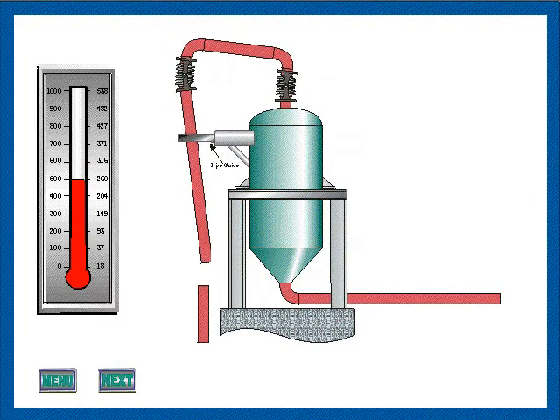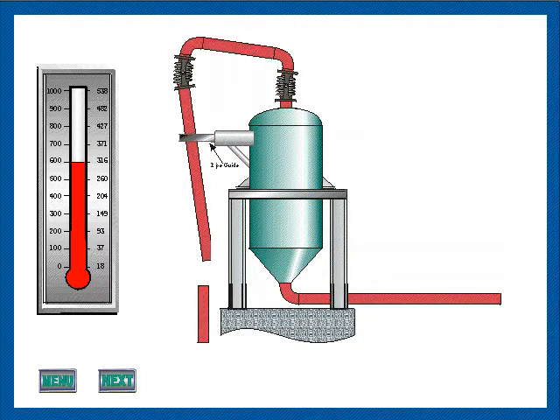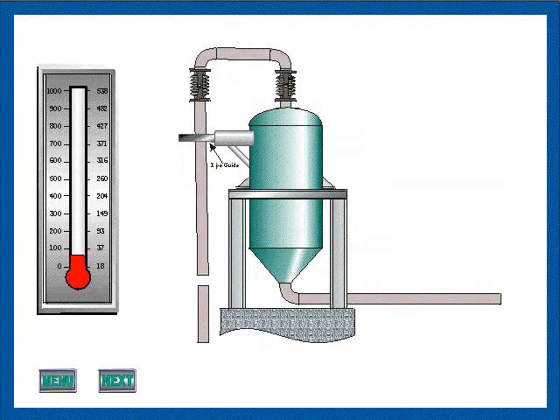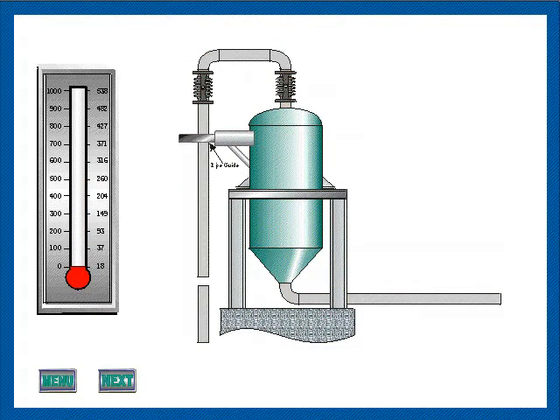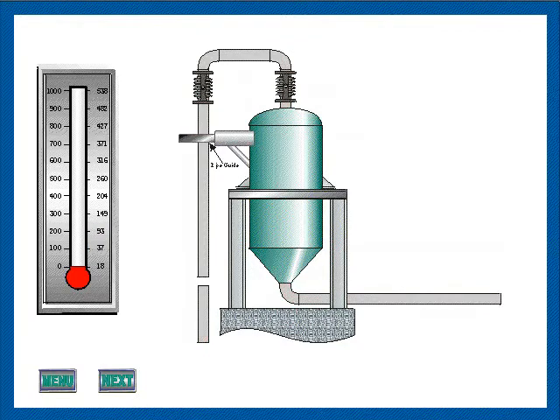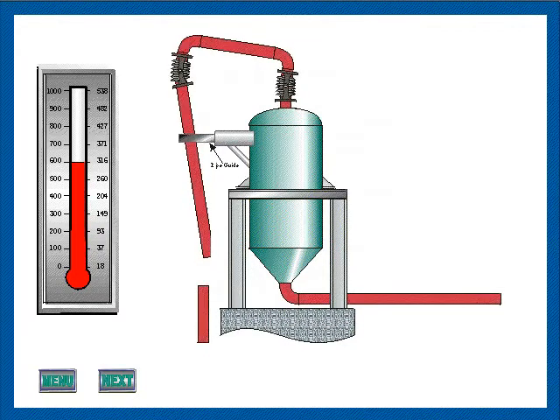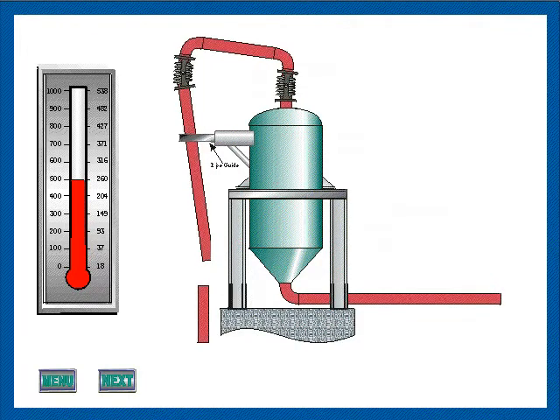Because of the ability of the hinges to transmit loads, support of a hinged piping system can be frequently simplified. Assuming this animation is an elevation view and that the upper piping leg is sufficiently flexible to absorb the total expansion of the vertical leg, it would be possible to use sliding supports on the lower horizontal run to support its weight and restrict it to longitudinal movement only.